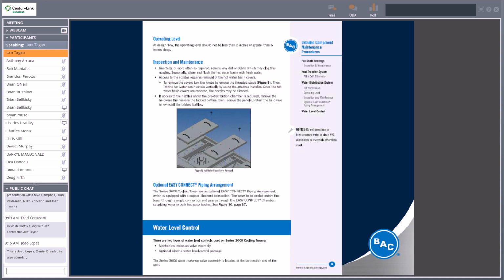Operating level, again, earlier in the O&M manual you saw how many inches it should be for different types of unit. You want to make sure it doesn't get too low because it won't have proper coverage. You want to make sure it doesn't get too high because then you'll start to overflow. And if you're running this during the swing seasons or during the winter, you'll get some ice buildup. During the winter, if you see ice buildup on the outside of your tower, which is very common in New England, a rule of thumb is if it's ice building from the top down, it's typically a balancing issue, and you've got too much water going to your cooling tower.